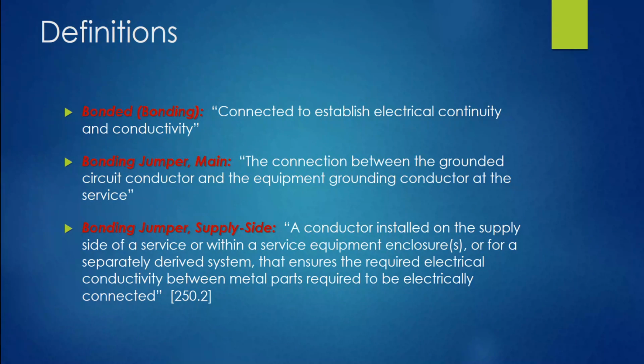All right, so we got to know some terms. Now, the first thing I'll tell you, when it comes to terms, they are critical. All the terms that you'll see are found in Article 100, except for the exception here of supply side bonding jumper. Now, supply side bonding jumper is found in 250.2. I will tell you, for the 2020 National Electrical Code, there was a public input to move it to Article 100. Why? Because the style manual says, in 2.2.2.1 of the NEC Style Manual, that if the definition is used in more than one article, it needs to be located in Article 100.